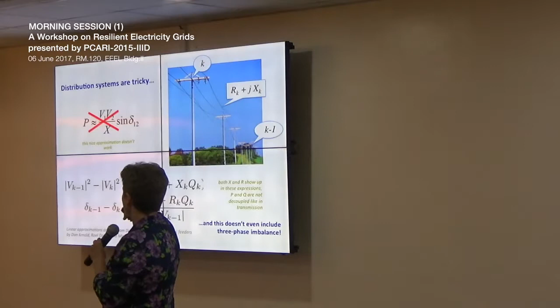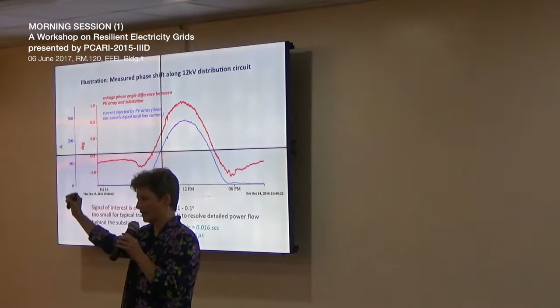So the red curve measures the difference in the voltage phase angle between the substation and the point of common coupling where the solar photovoltaic plant interconnects. And you can see, if you look at the axis, that ranges from somewhere around -1 degree to +1 degree. So that's our entire range, and that's for a lot of power flow. That's several megawatts. And our micro-PMU is basically measuring the precise timing at the two locations and then taking the difference of the angles. So it's measuring very precisely how that angle tracks.